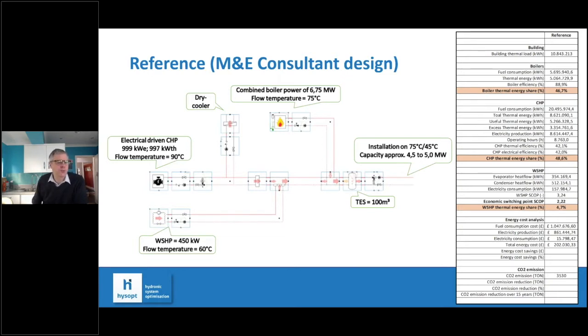On the right-hand side of the screen we can see the kind of metrics the simulation gives us. The boiler has about 47% thermal energy share, working at about 89% efficiency. We can see all the gas consumption and so on. The CHP has about a 49% thermal share as well, and that's being used to generate electrical power at the same time. Our heat pump is really not doing much at all, about 5% of the overall thermal share, with a seasonal COP of about 3.2. At the bottom we can see all the energy costs - total energy cost is about £200,000 per year, and carbon emissions of about 3,500 tons.